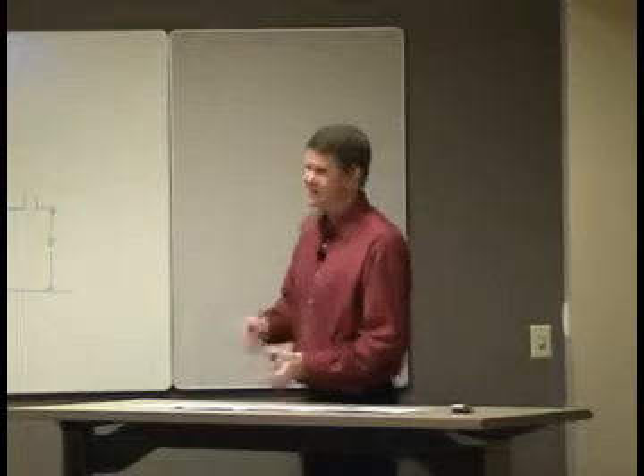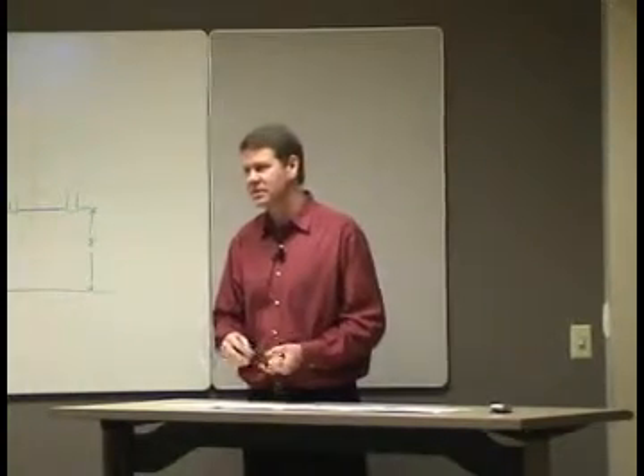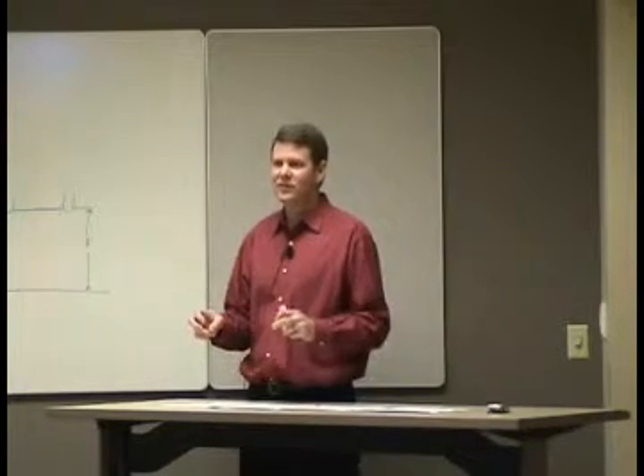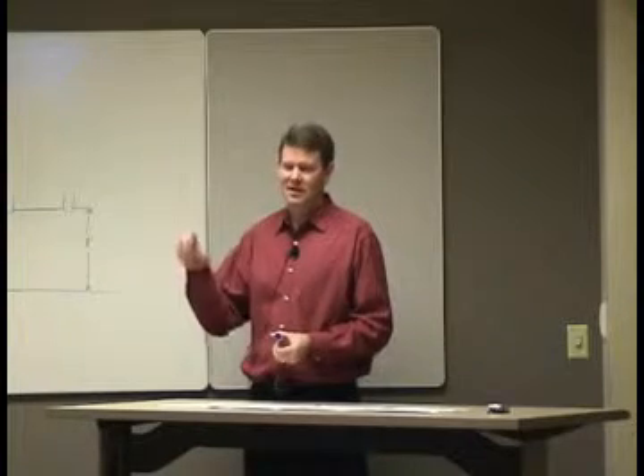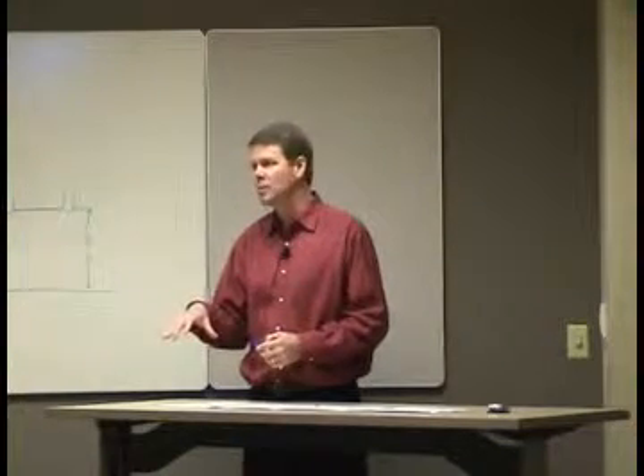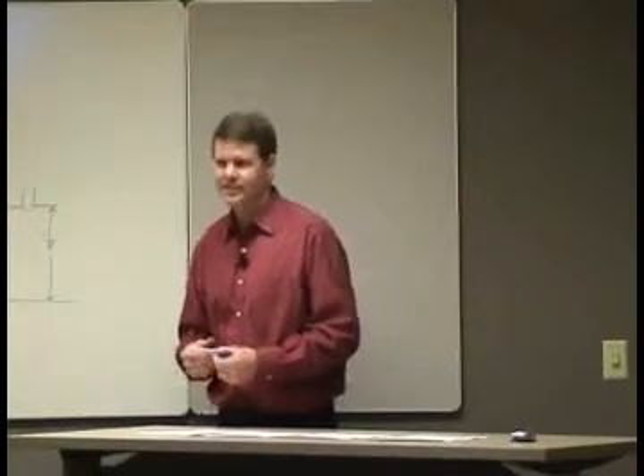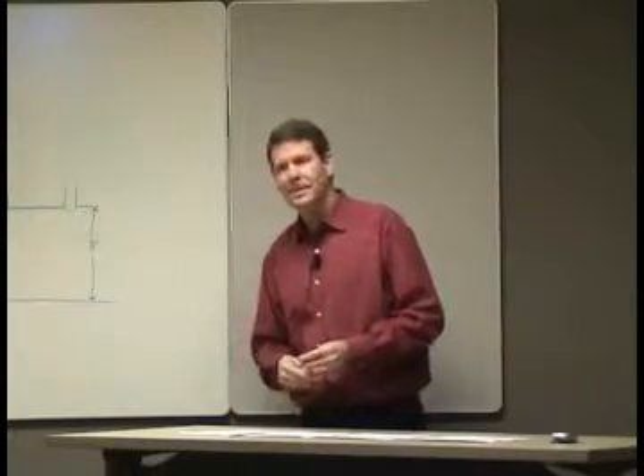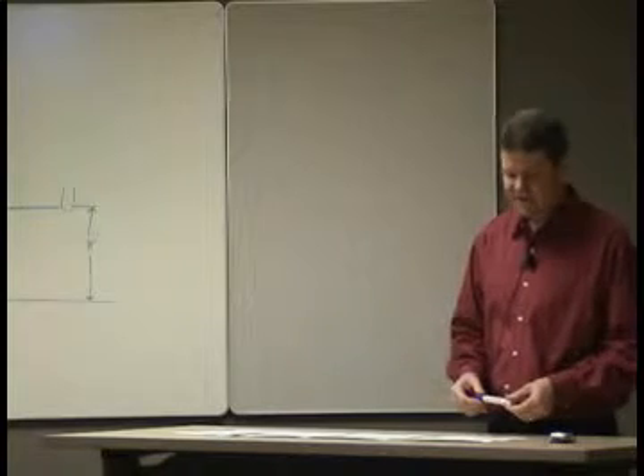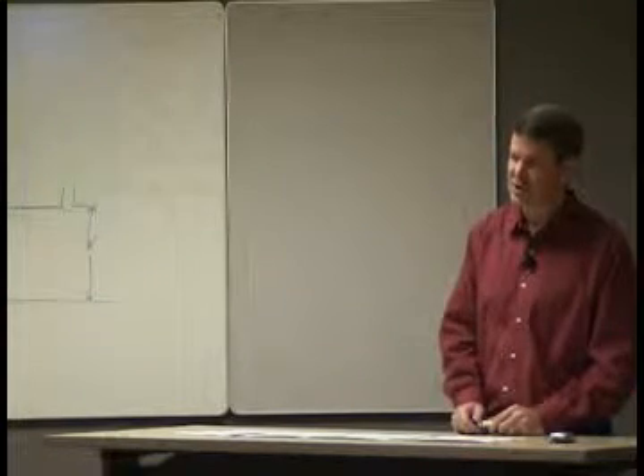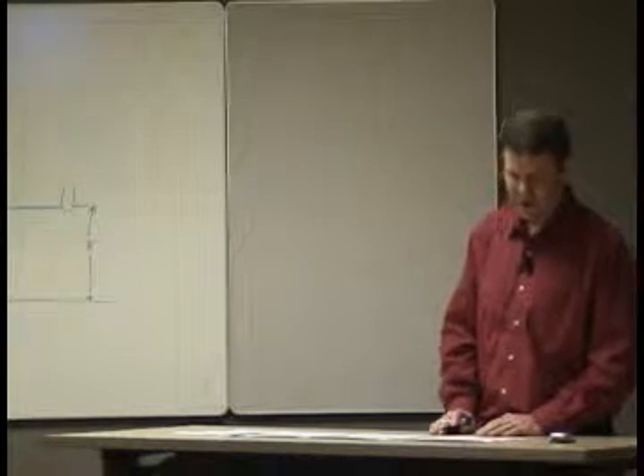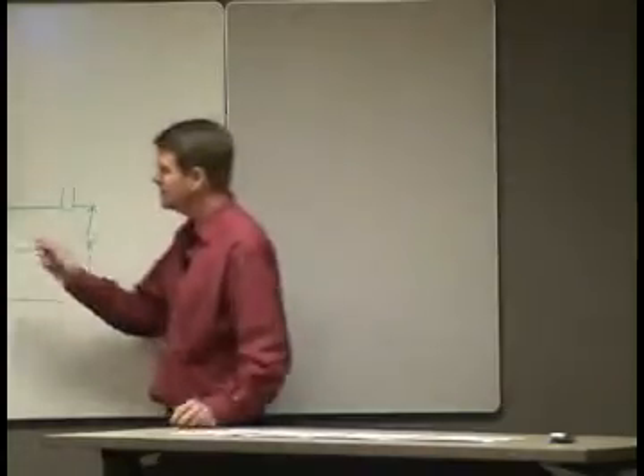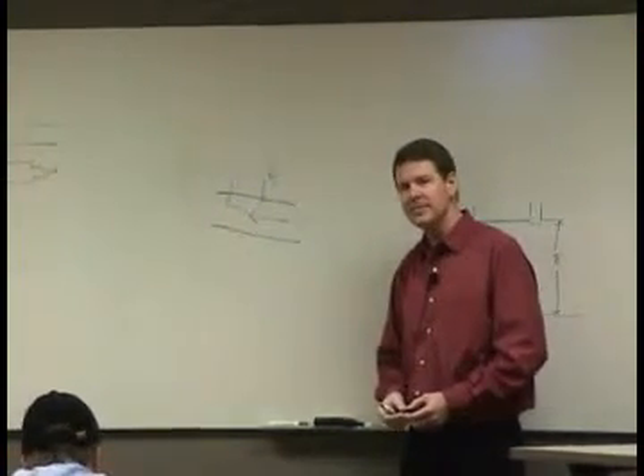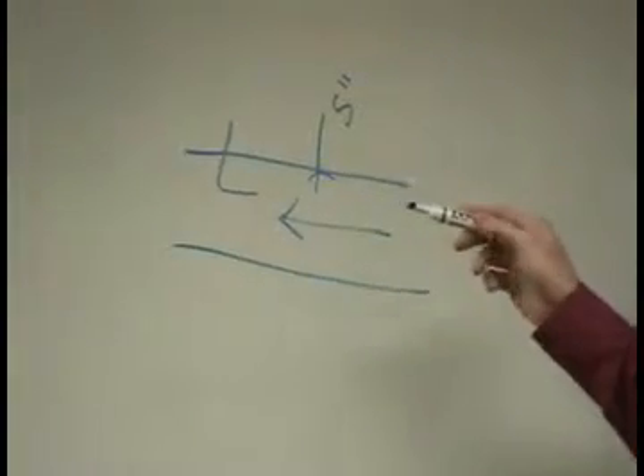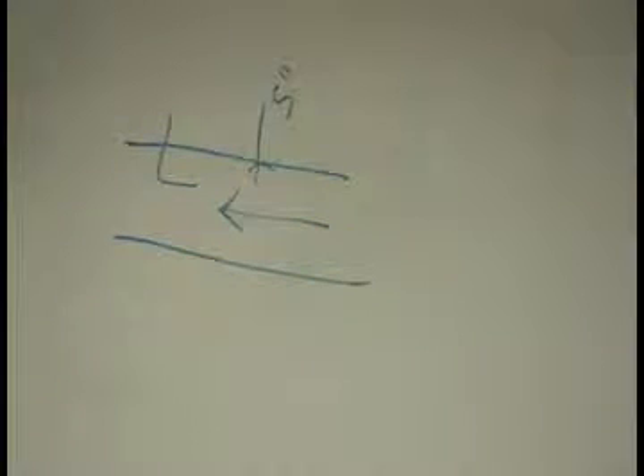What we've got to do is take velocity pressure and make it mean something to us. What we're normally concerned about is cubic foot per minute. As the engineer tells us, you give me 1,000 cubic foot per minute into the room and it'll be comfortable. That'll be enough to cool it. So the formula here is 4,005 times the square root of the velocity pressure in inches of water column. That's going to tell you how many foot per minute you have of air shooting down the duct. Then if you multiply your foot per minute times your square foot of duct area, that's going to give you cubic foot per minute.